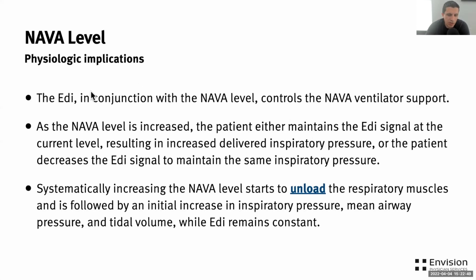So what are the physiologic implications of choosing the right NAVA level? So remember that the NAVA level controls the level of ventilatory support. As the NAVA level increases, the patient can either maintain the EDI signal at the current level, resulting in increased delivered inspiratory pressure, or the patient can decrease the EDI signal and say, you know what, you're doing all the work, I'm good, just keep doing what you're doing. Systematically increasing the NAVA level will create something called unloading on the respiratory muscle and is followed by an initial increase in the inspiratory pressure, mean airway pressure, and tidal volume while the EDI remains constant.